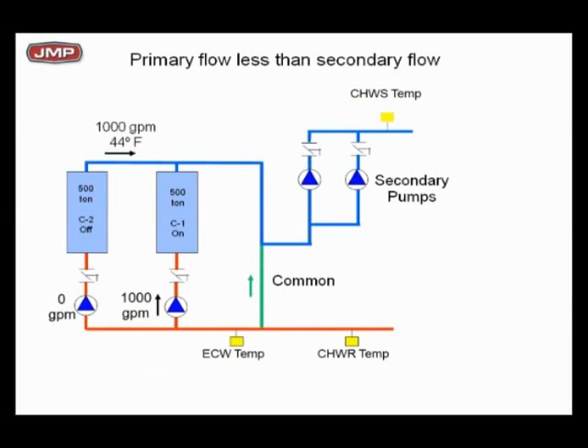I've got one chiller running, 1,000 GPM, 44 degrees. Chiller number 2 is off. What happens, or can I take out 1,200 GPM? Wow, interesting, huh? You telling me I'm going to take out more water than I'm putting to the T? Yeah. Now, what does that mean to you? What have you learned? What's happening in the common pipe? That means I got 200 GPM going north, bottom to the top of the screen on the common pipe.